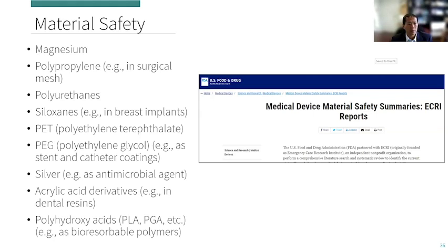The FDA was also interested in resorbable materials such as PEG, or polyethylene glycol, typically coating materials used on stents and catheters. Silver was also another material that drew the FDA's attention for its use as an antimicrobial agent. There were also acrylic type materials, such as those used in dental resins, that the FDA was interested in. And then lastly, bioresorbable polymers, such as PLA or PGA, also drew the FDA's attention.